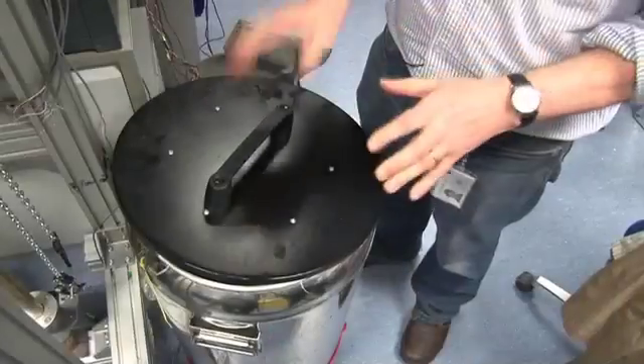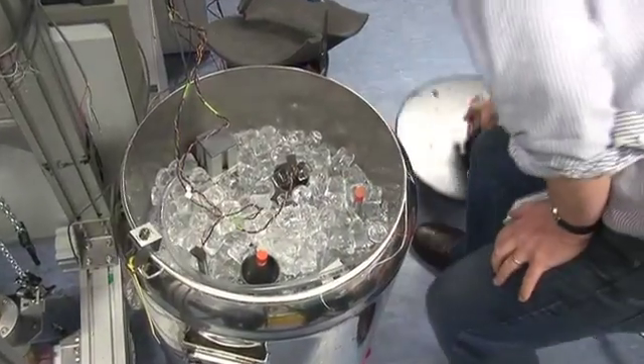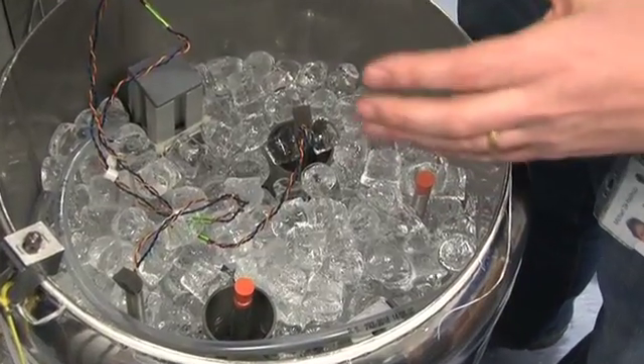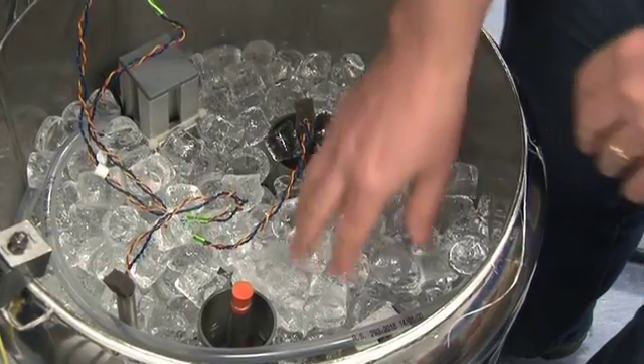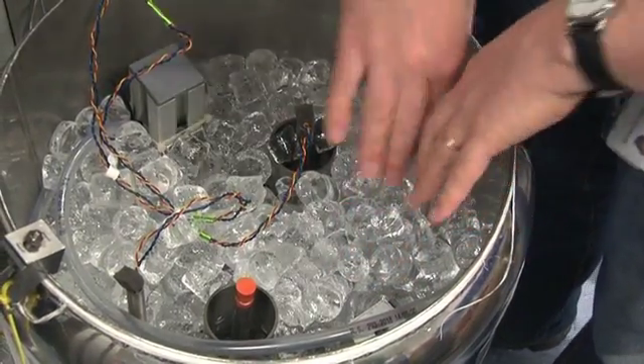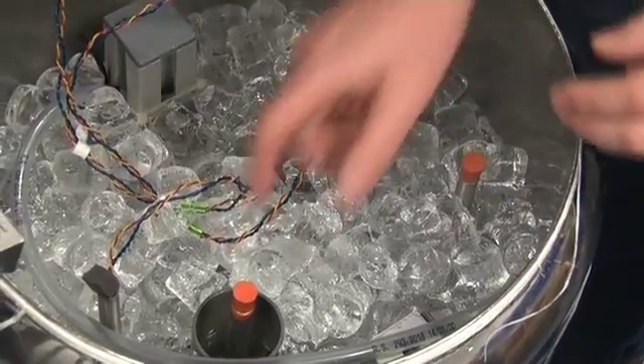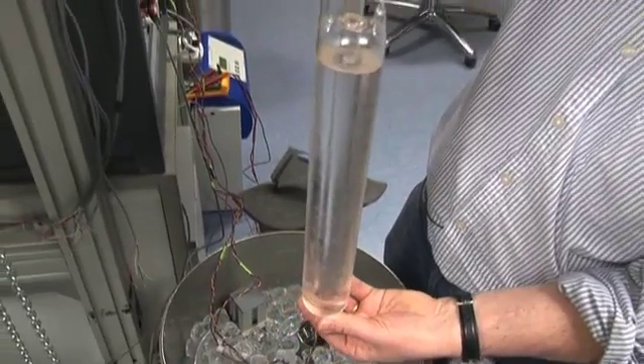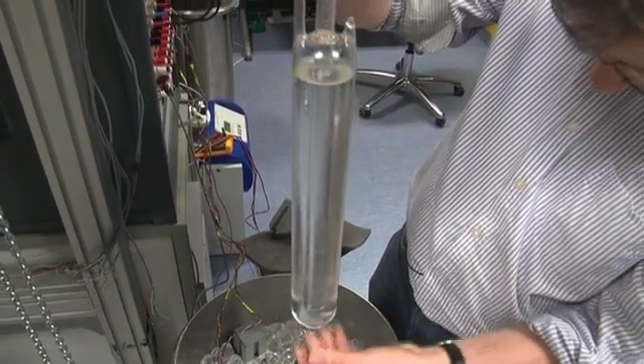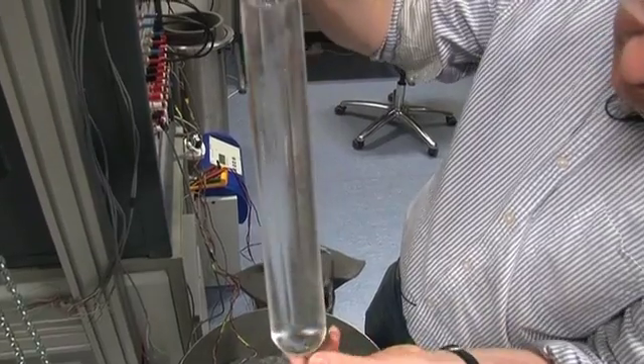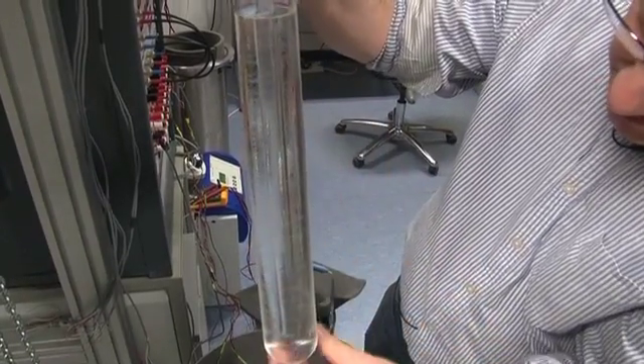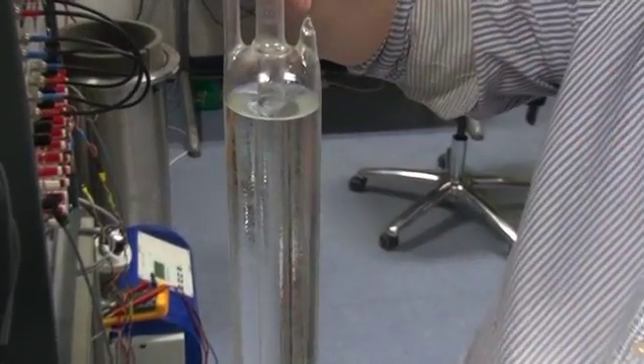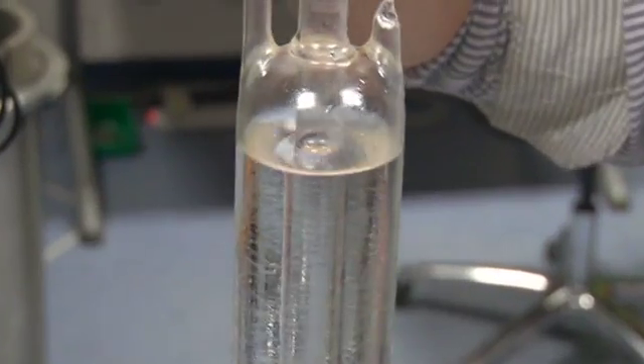Inside this insulated container are cells, glass containers containing water held at the temperature of the triple point of water. You can see here's ice, so around here is about zero degrees Celsius. Inside here it's a little bit hotter. This is a triple point of water cell and it contains liquid water. Around the core of it you should be able to see some ice, that's solid water. And up at the top here is water vapor, all three phases of water substance.